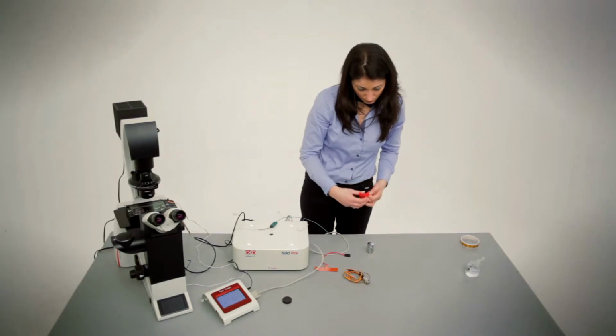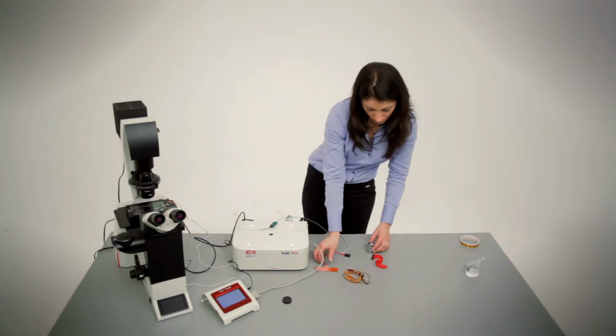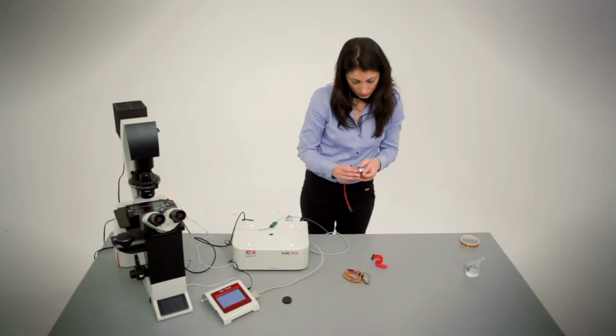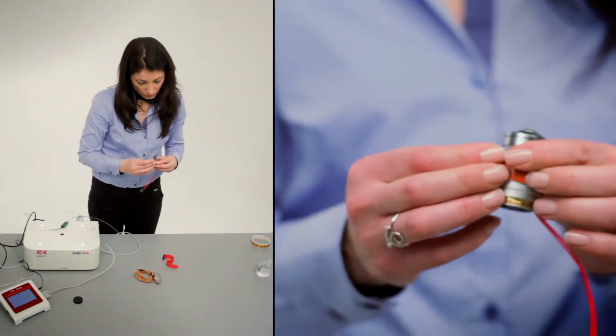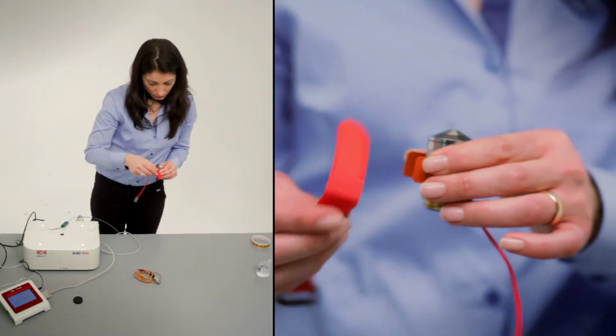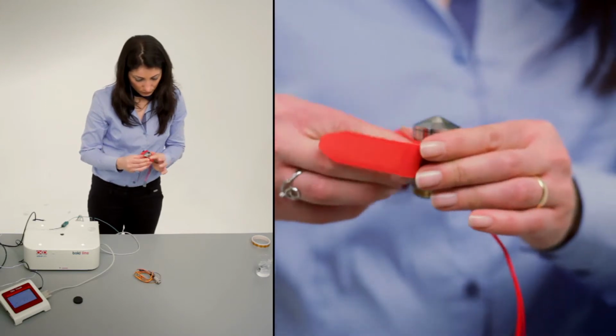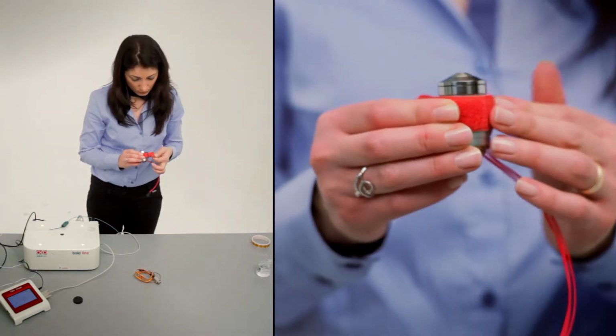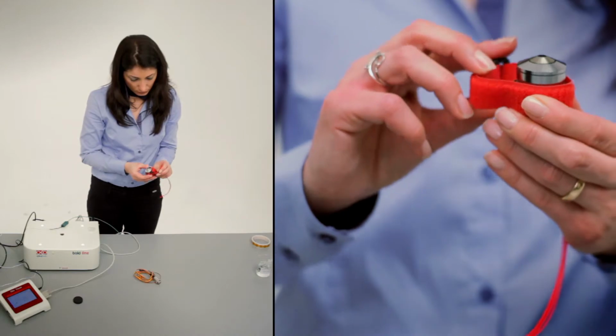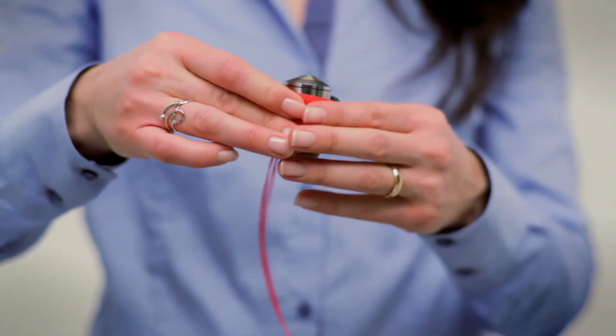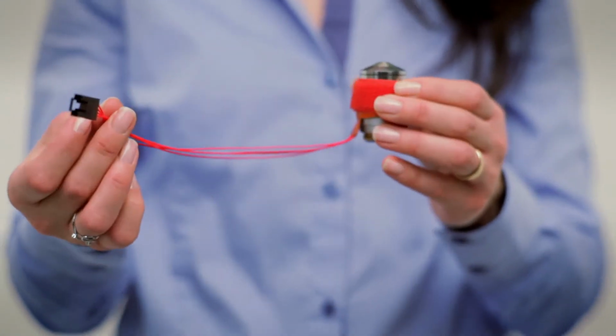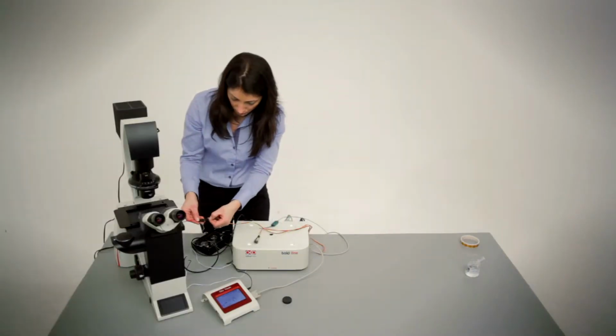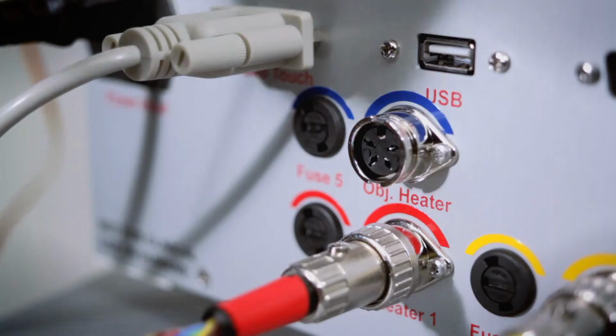Oil immersion and dipping lenses should be heated up to avoid undesired sample cooling during imaging. For this reason, the Boldline Top Stage Incubator has a built-in objective heater. To install the objective heater, select the proper band according to objective diameter, fasten it around the objective with the corresponding Velcro tape, and connect the cables to the temperature controller.